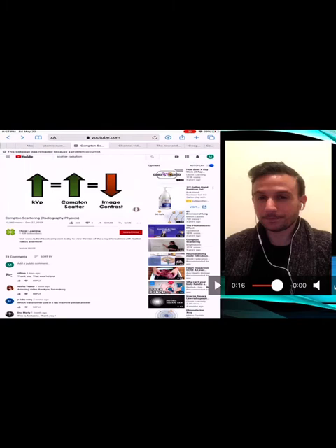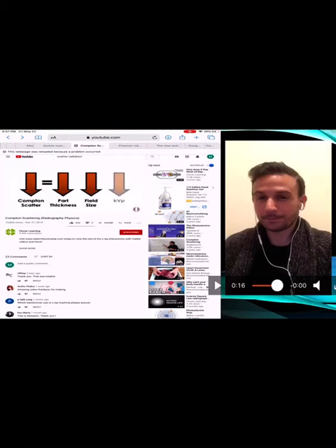The ideal situation would be to have as little scatter radiation as possible. So how can we reduce the amount of Compton scatter? Consider these factors. We could decrease the part thickness. We do this by compressing the patient if possible. We would also want to use the smallest field size or the most collimation possible. And last of all, when we can, we'd want to use a lower kVp. All of these factors together decrease the amount of Compton scatter taking place.